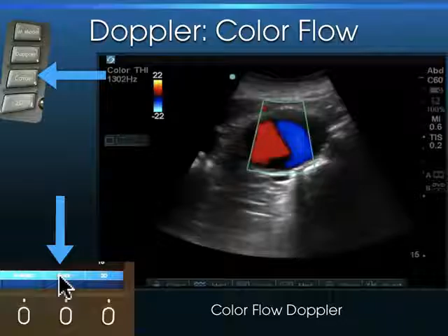Yes? Can you just, to get this in my head, the top of the screen would be the transducer? Correct. Exactly right. This is the skin line of the transducer, the footprint of the transducer right there. And the way we activate this flow, we come down here after we hit mode. Here are the different modes. Well, there's 2D, which is just straight up brightness mode. There's color, which is what we're seeing here. So you're going to activate that color, and then you're going to see this gate, this color box pop up on the screen, and you're going to place that over the valve.